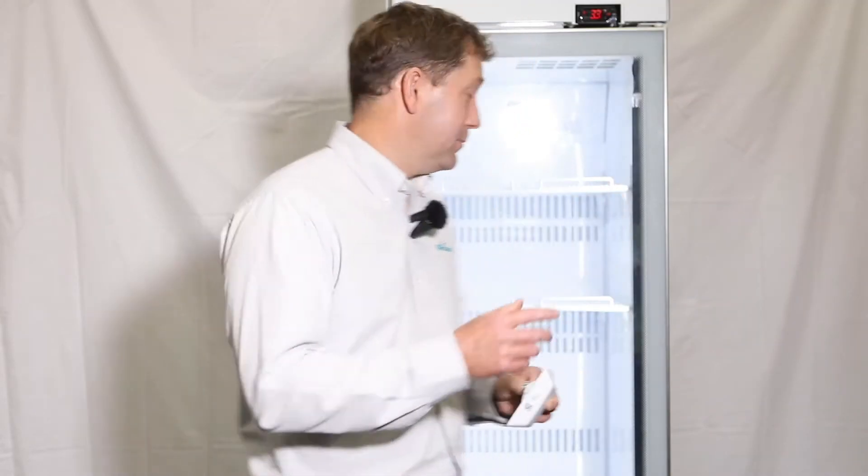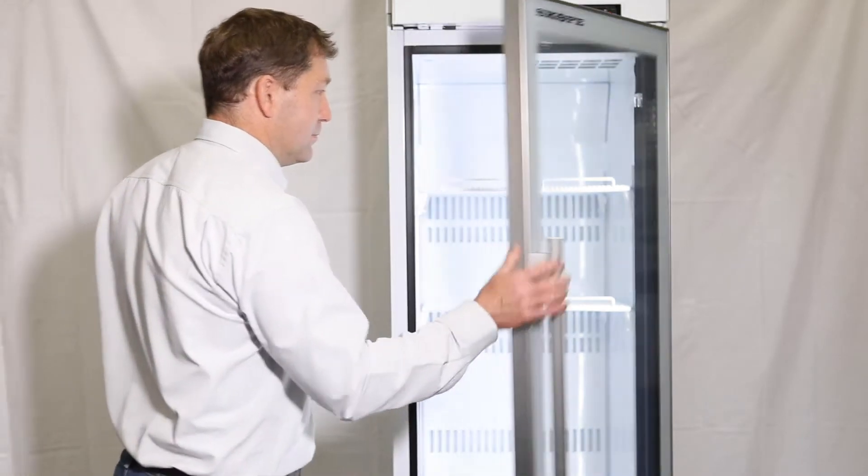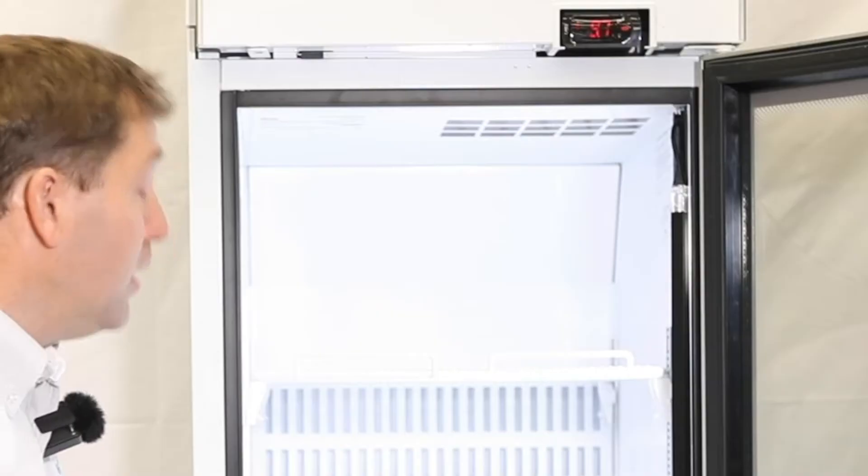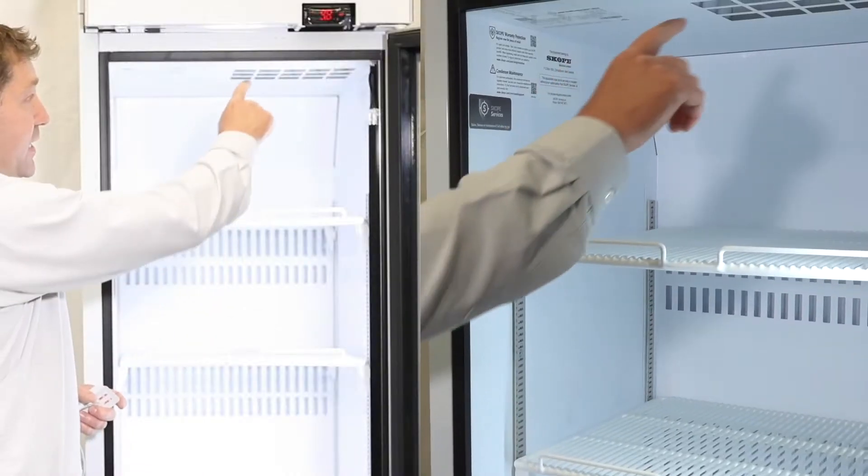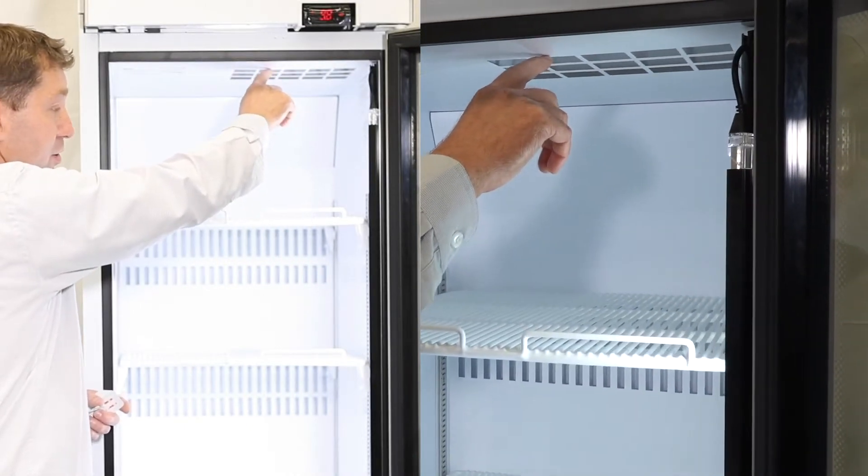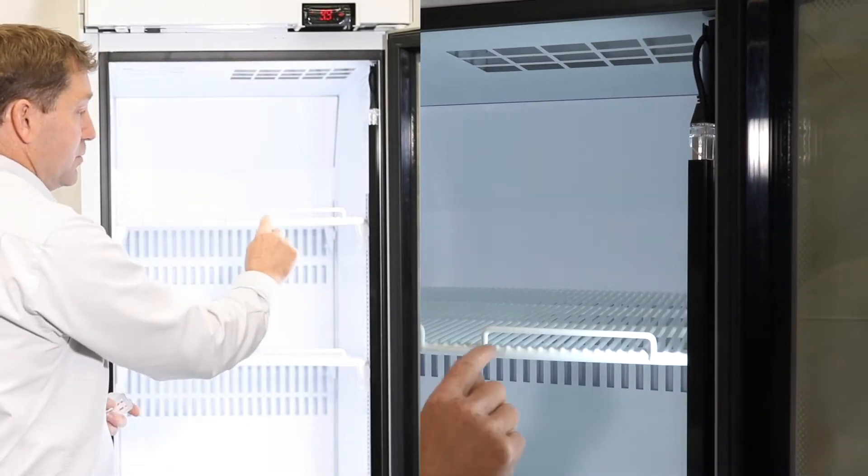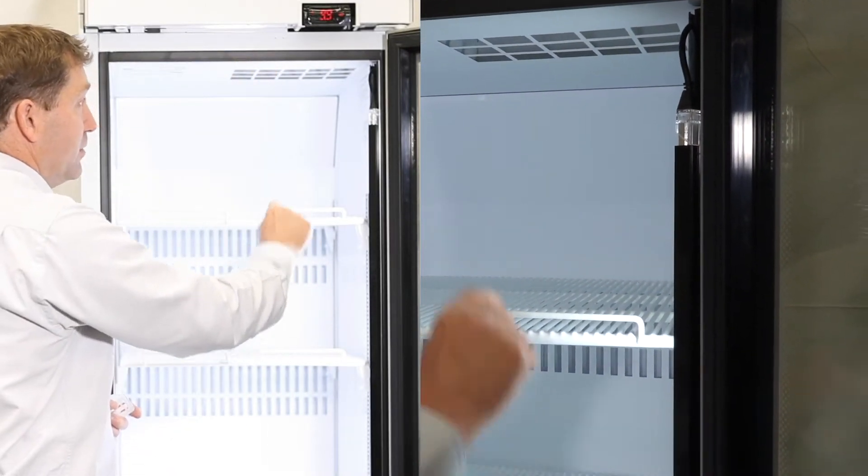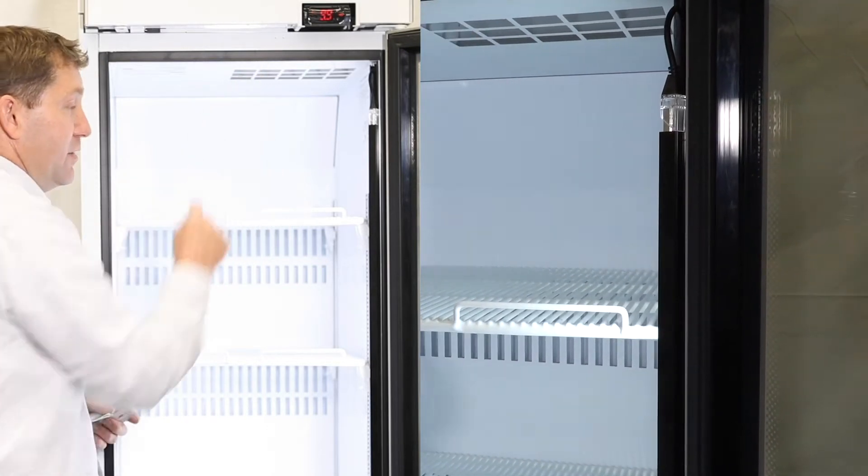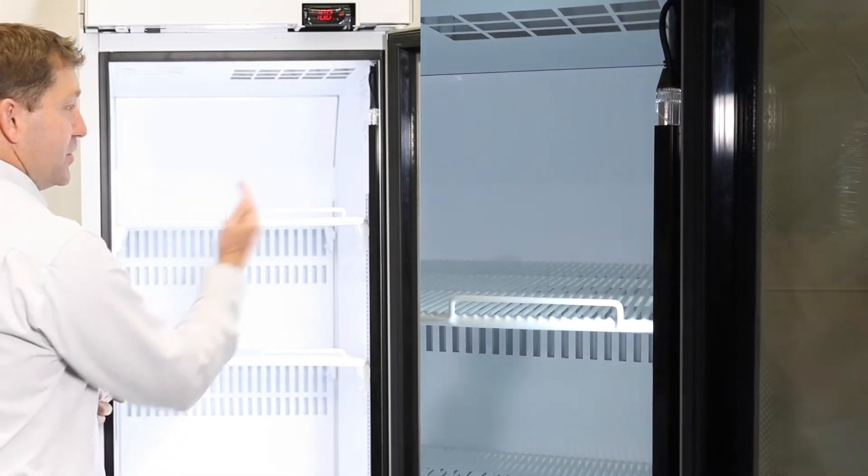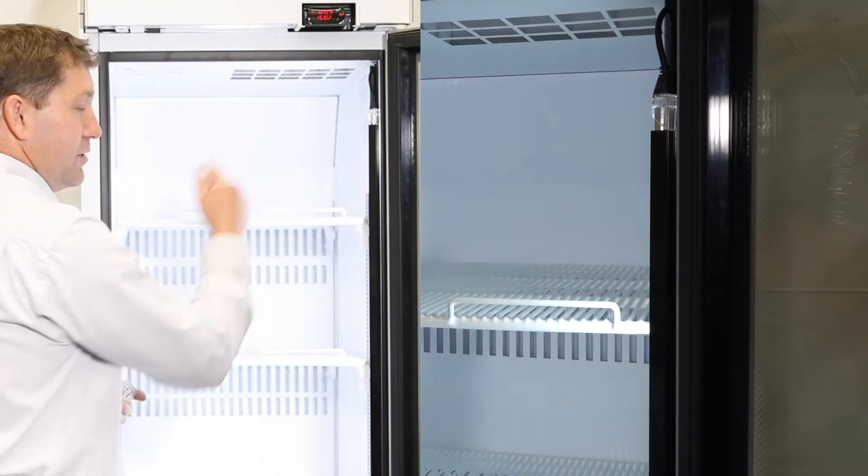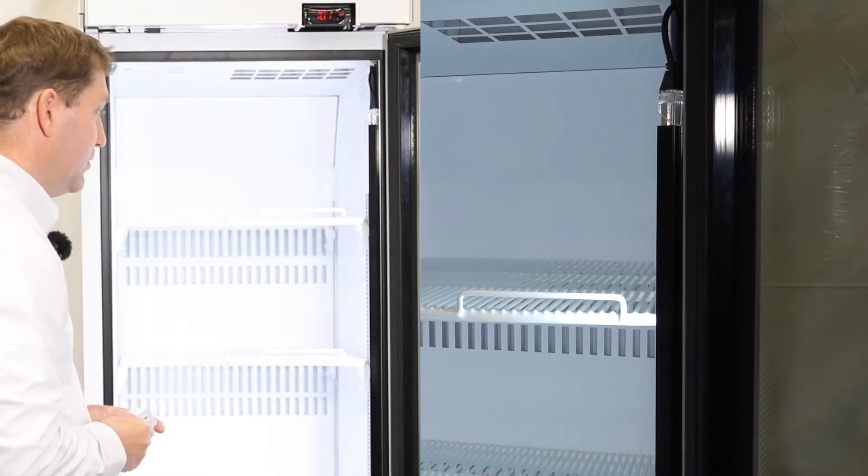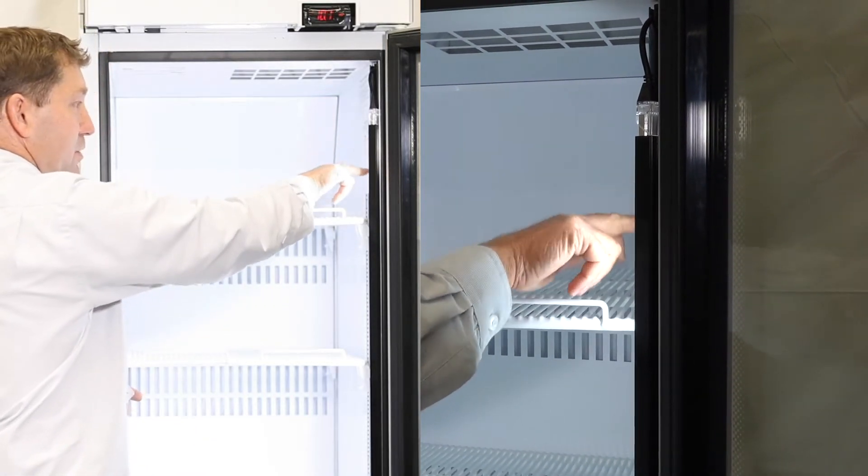Now I'll demonstrate how to do an installation. For this particular fridge, the air inlet for the evaporator is at the top, so we want to be mounting it between the top shelf and the inlet for the evaporator. It's also beneficial to mount it on the hinge side so it is less intrusive. Therefore we'll be mounting the monitor just here.